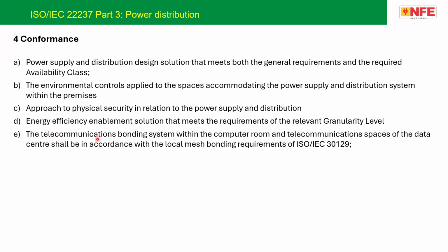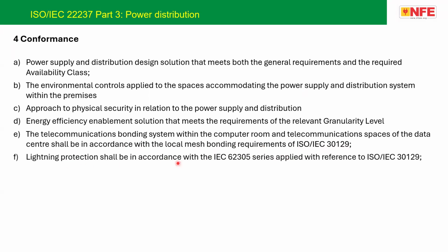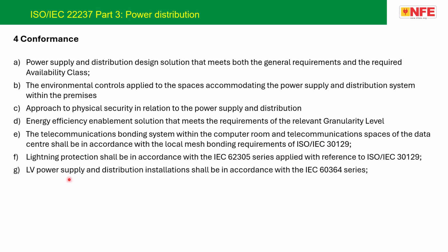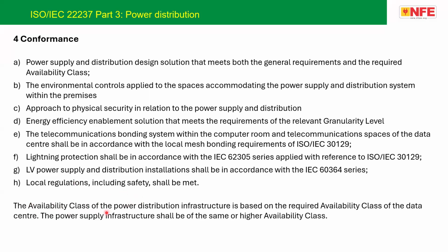Salim told. The telecommunication bonding system within computer system shall be, you can see here, in accordance with local mesh bonding requirements of ISO 30129. Lightning protection shall be in accordance with 62305. LV power supply and distribution shall be in accordance with 60364. Local regulations, if any, that also shall be met. The availability class of power distribution infrastructure is based on required availability class of the data center. Power supply infrastructure should be same or higher availability class.